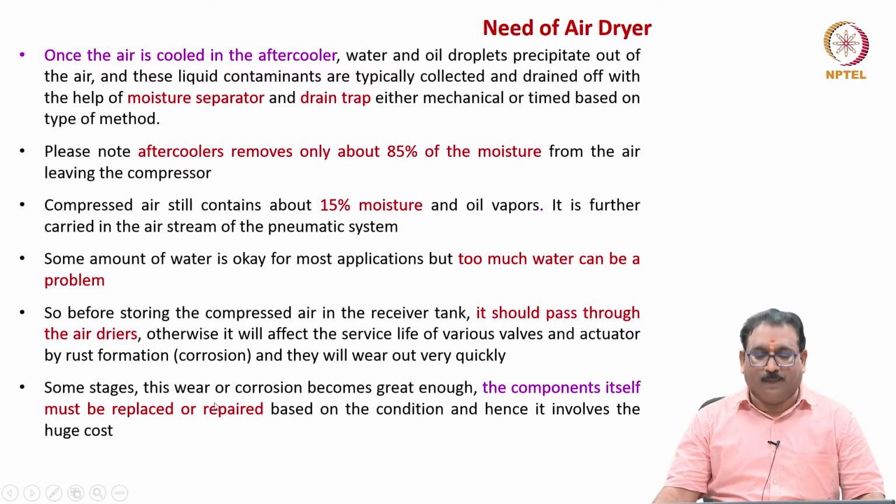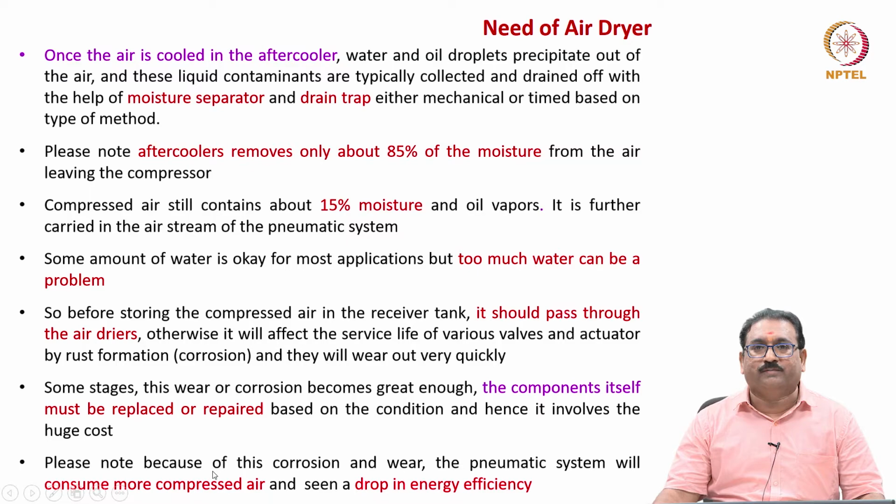At some stage, the wear or corrosion becomes great enough that the components themselves must be replaced or repaired based on the condition, and hence it involves huge cost. Please note, because of this corrosion and wear, the pneumatic system will consume more compressed air and see a drop in energy efficiency. That is why we have to use the air dryer during air preparation.